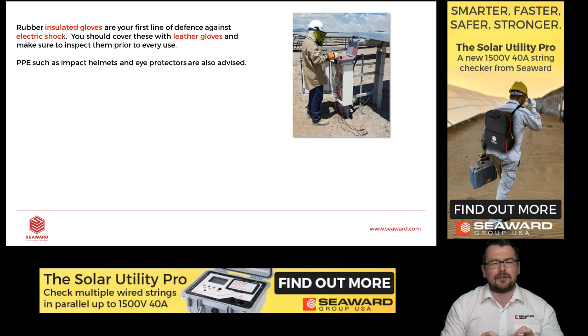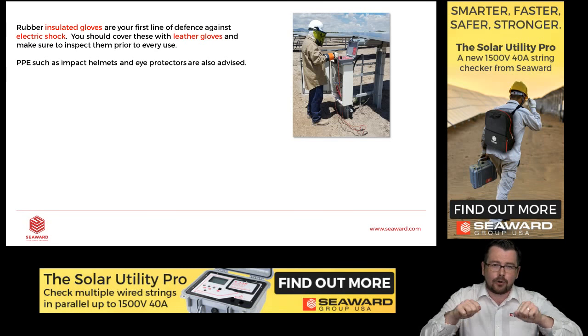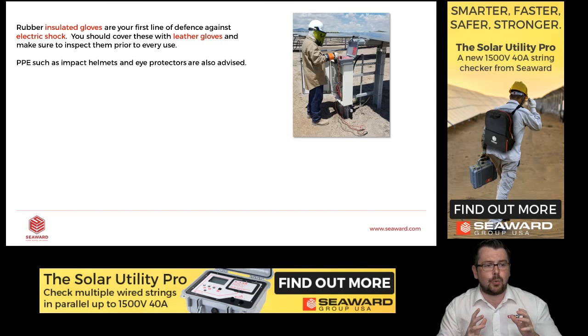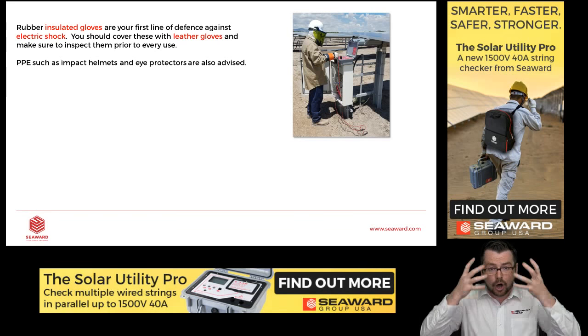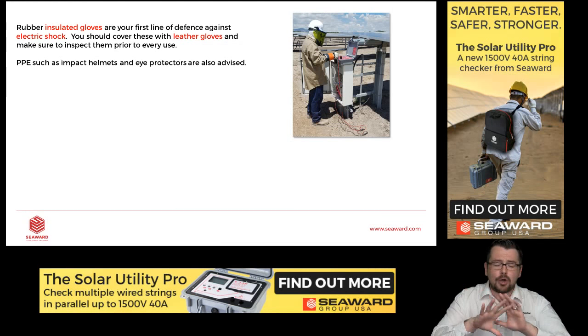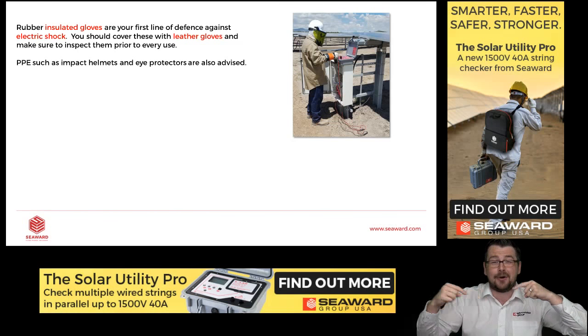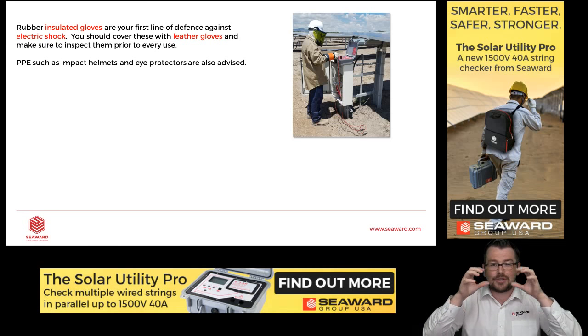With this in mind, there are some very basic measures you can take towards electrical safety, and if you're used to dealing with AC systems, maybe in commercial buildings or in residential homes, DC is slightly different, so you should take extra care. It can arc a lot more. So I would suggest rubber insulated gloves as your first line of defense, and consider covering these with leather gloves. This will give you an initial protection with your hands where you're actually inside the combiner box or at the solar panels themselves. And also you should wear the appropriate personal protection equipment with regard to arc flash protection, helmets. When you're walking around a solar farm, there's lots of steel pointing out everywhere, or aluminium, which could poke you in the eye. So it's always good to have eye protection as well.